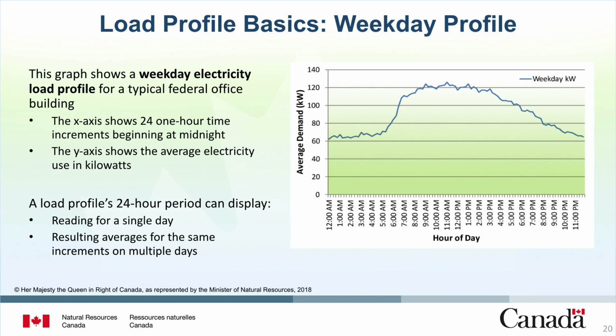As displayed by the load profile, electricity use for this building hovers around 65 kilowatts during nighttime hours. This baseline energy use appears to be higher than it should be. Building startup usually occurs around 5:30 a.m. System startup times are typically in advance of the building's scheduled occupancy. This is done to provide acceptable conditions for occupants upon arrival. Building operation continues to ramp up as different HVAC, lighting, and plug load systems engage until about 8 a.m. when energy use begins to level off.